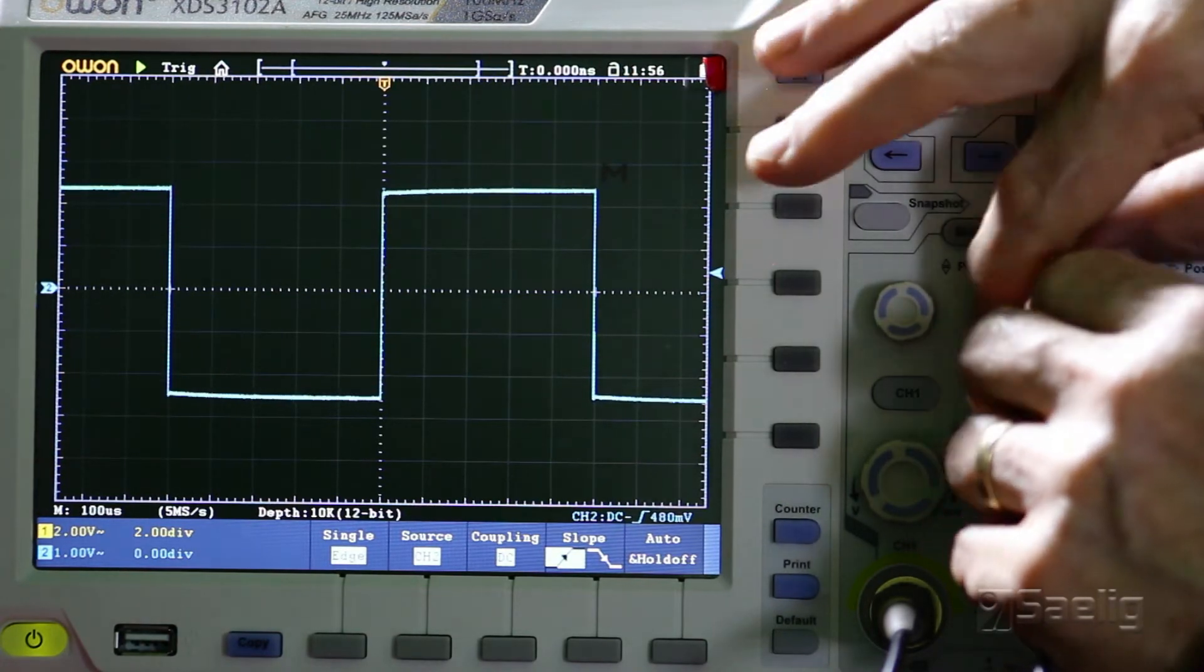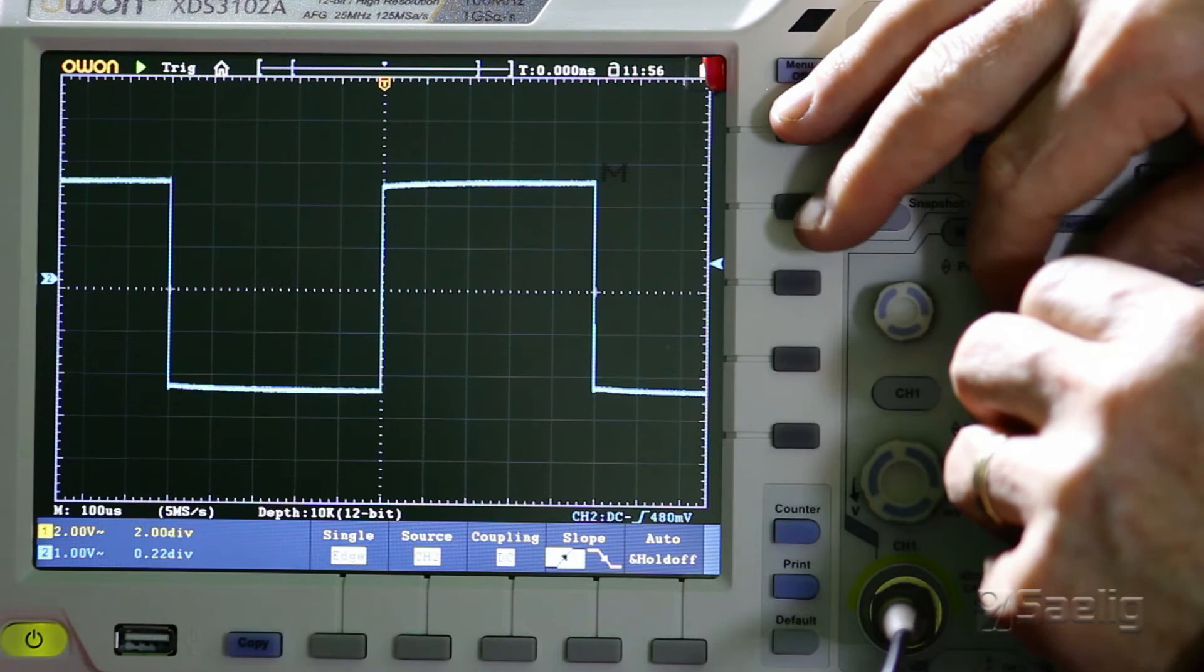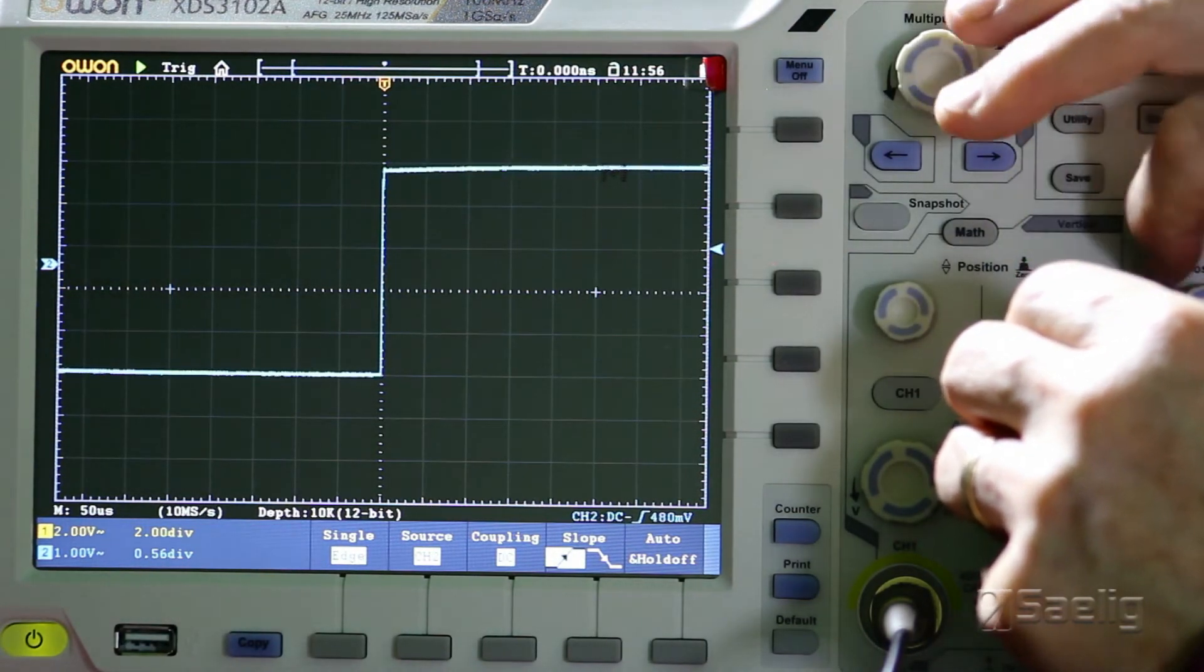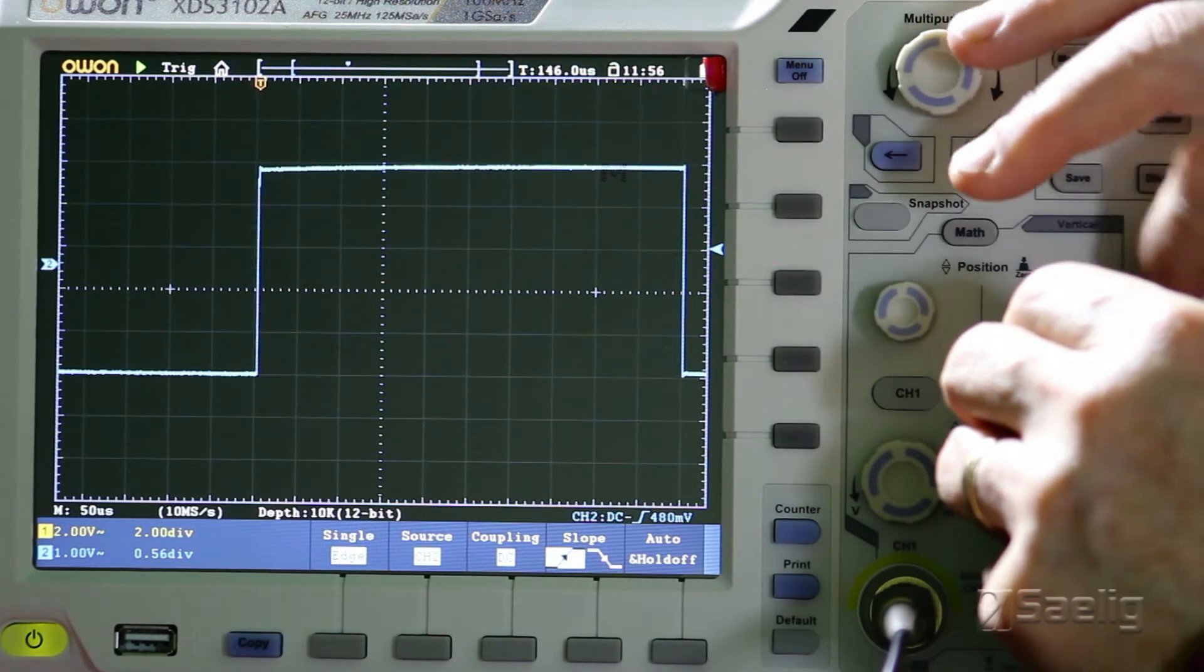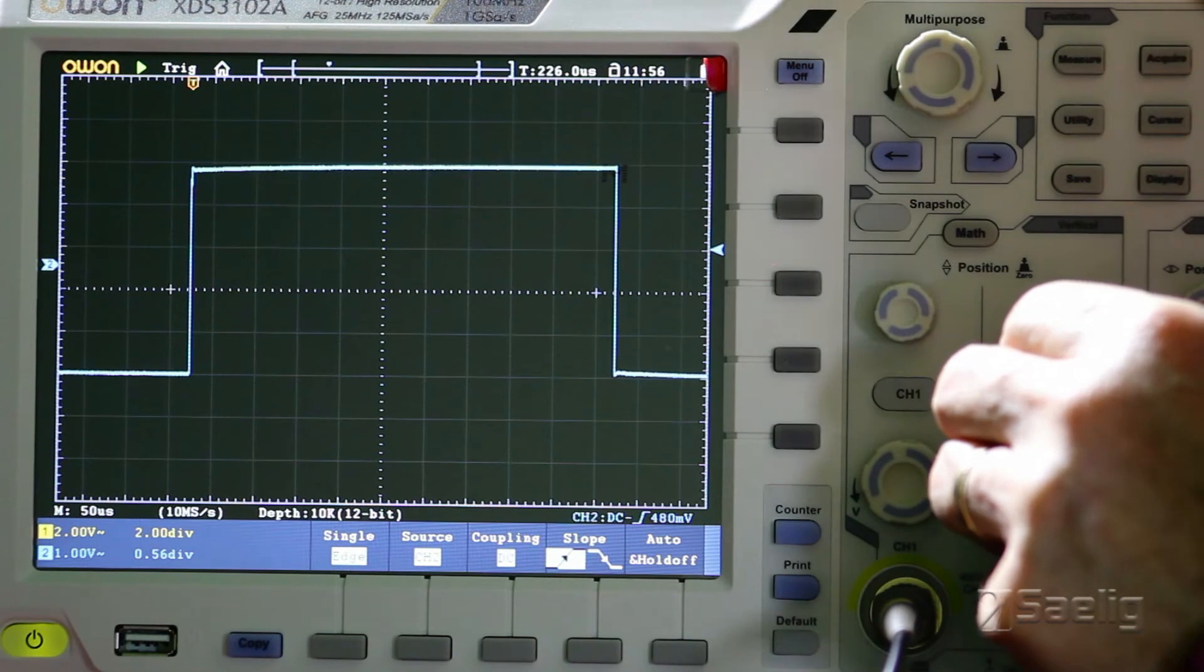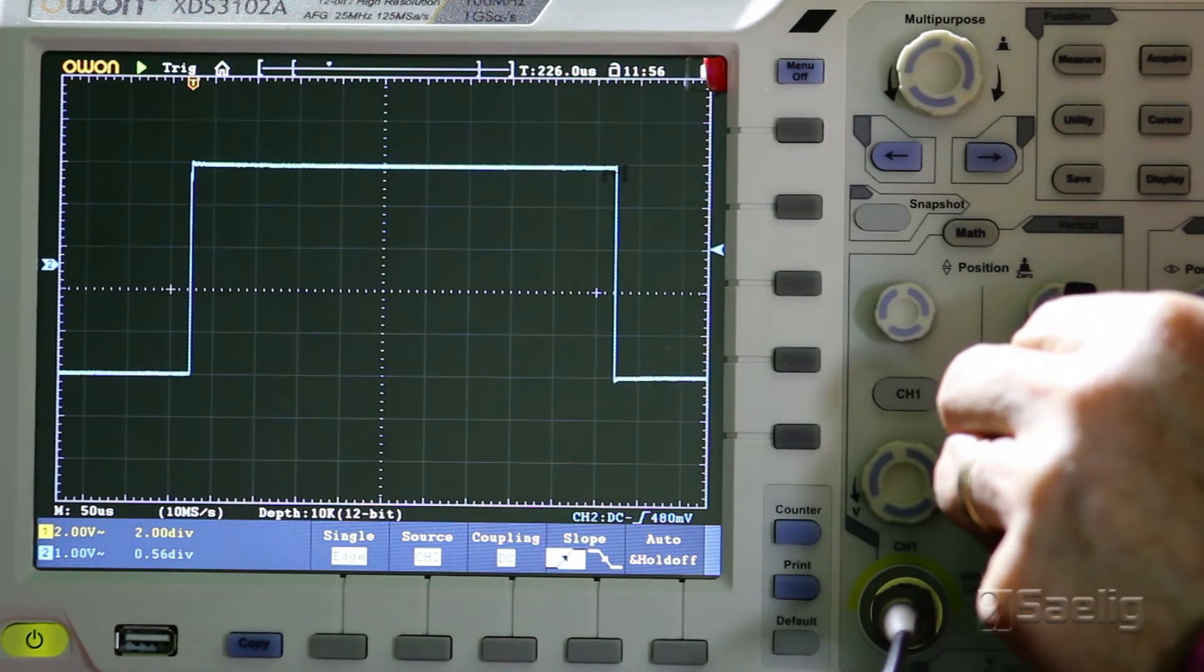What we want to do is bring that up. So I use a level line or one of the horizontal lines here so that I can make sure I've got it level. And I'm going to stretch this out so it's as long as possible. Let's move the trace over to the center of the screen and let's get that trace to match the line on the graticule as closely as we can right here.